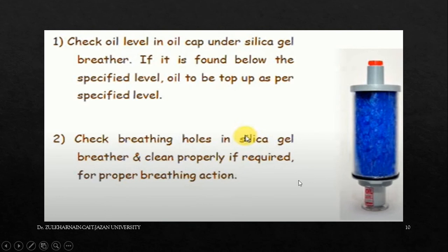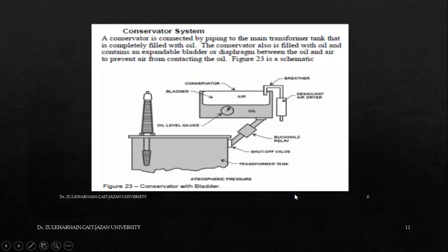Similarly, there are different things which are useful for doing it. This is called silica gel breather. This is used for breathing holes in the transformer. Another important device is the conservator system. As you can see here, you have air, you have oil, level gauges, and this is called breather. And in this way, we are able to maintain the cooling system for a transformer.